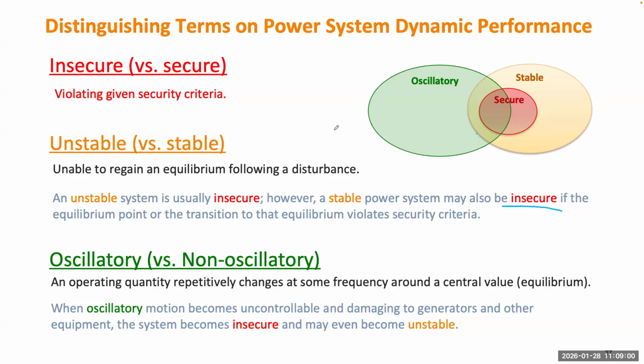Knowing those terminologies, when you talk to other engineers, now or in the future, you can make sure your statements are accurate. You always hear some engineers say, okay, my generator is oscillating, so that is unstable. Sometimes that may not be true. You have to ask for more details: whether the generator finally goes to a new equilibrium, and whether there is any violation of your standard. Then you can make a more accurate statement about that phenomenon.